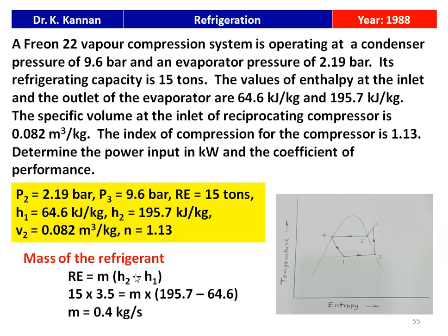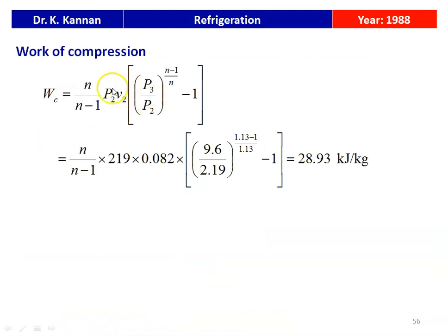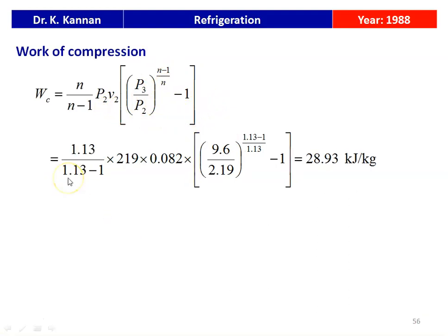The mass flow rate of the refrigerant is calculated from the given refrigeration effect. Refrigeration effect equals mass into enthalpy change across the evaporator. So, 15 tons, where 1 ton equals 3.5 kJ/s, gives 15 × 3.5 = M × (195.7 − 64.6). Solving, the mass flow rate M = 0.4 kg/s. The work of compression: Wc = (N/(N−1)) × P2V2 × [(P3/P2)^((N−1)/N) − 1]. Substituting: Wc = (1.13/0.13) × 219 × 0.082 × [(9.6/2.19)^(0.13/1.13) − 1] = 28.93 kJ/kg.